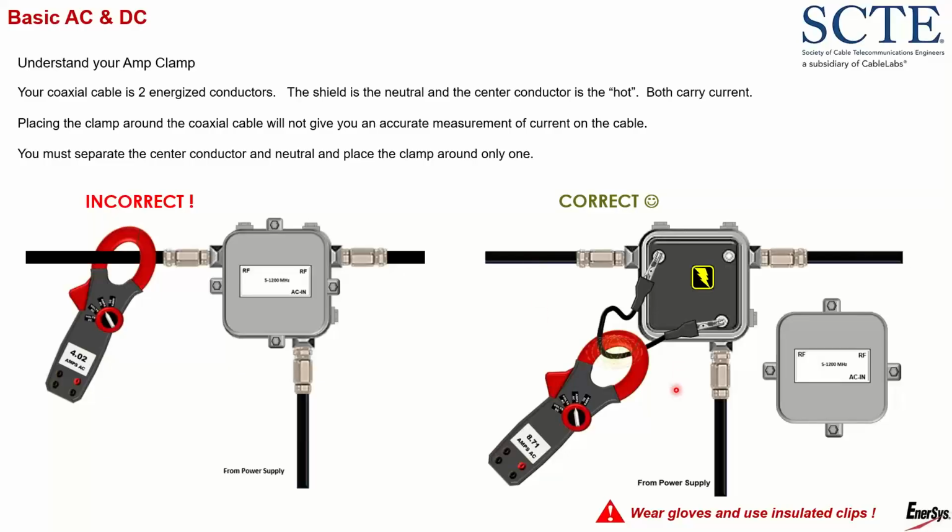Now, some guys also said, well, if I do this, it's going to cause an outage. Well, the only time you're going to do something like this is when you're out there tracking a problem, and the problem that you're tracking in this case is probably going to be a short or an overload, which means you already have an outage.